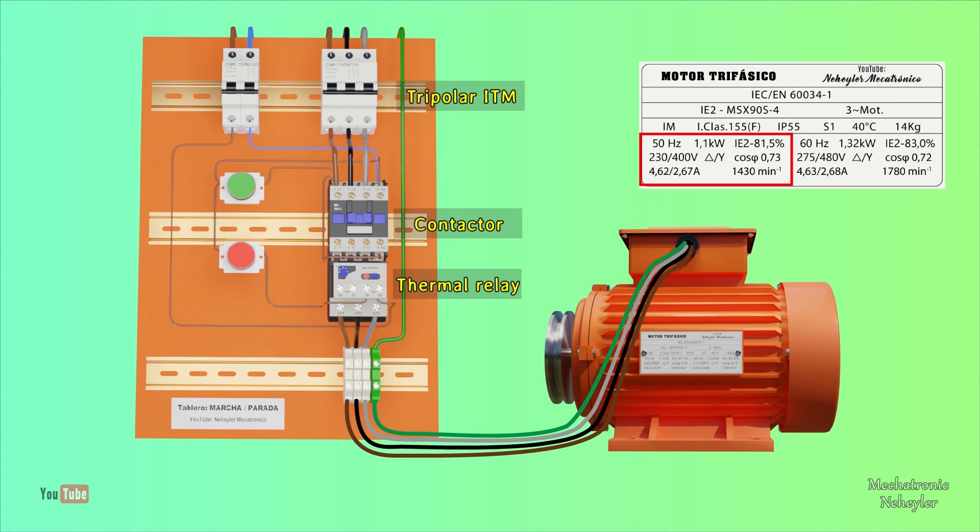The thermal relay is the element in charge of protecting the motor, therefore its current must be adjusted to the value of the rated current of the motor. For this case at 2.67 amps, or at its closest value of 2.75 amps.